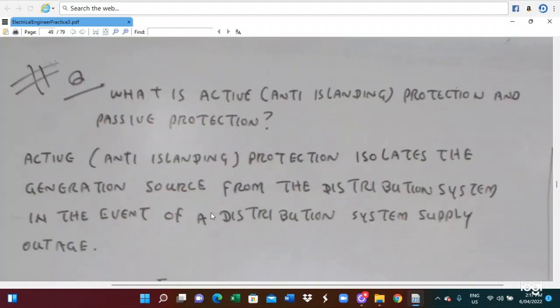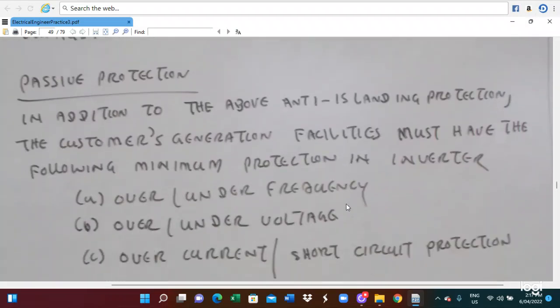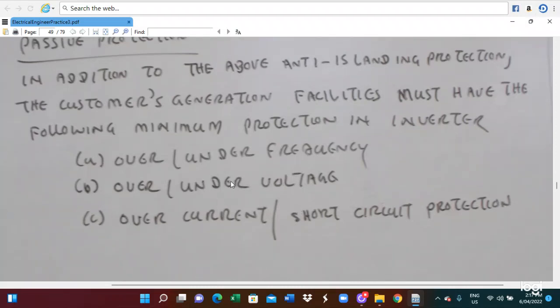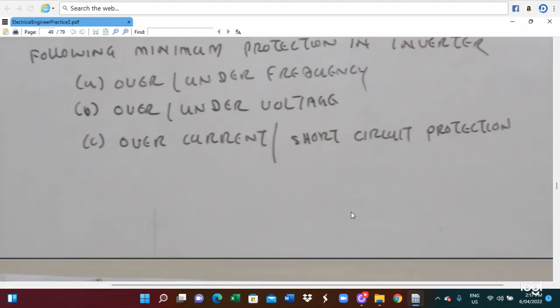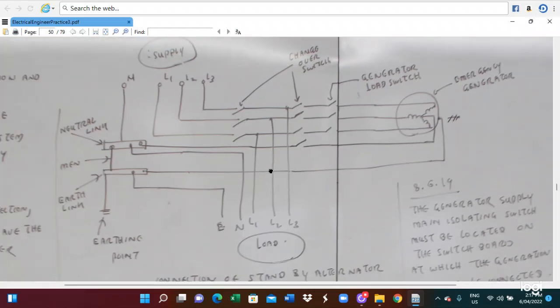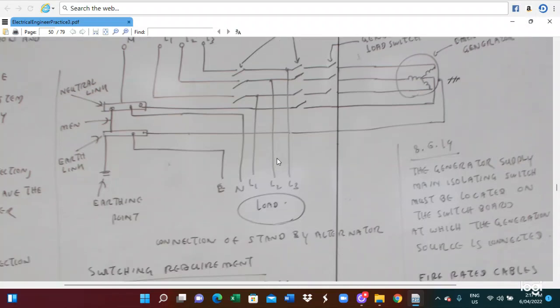What is the difference between active anti-islanding protection and passive protection? Active island protection isolates the generation source from the distribution system in the event of distribution system supply failure. Passive protection, in addition to the above anti-islanding protection: the customer generation facilities must have the following minimum protection in the inverter. They must have over and under voltage and frequency protection, over and under voltage sensors, and overcurrent and short circuit protection. Those are the requirements. So this is the diagram of the three-phase generator, load, and changeover switch, and the supply connection. This is the main neutral link, the earth link, the load, the generator, and the supply changeover. Emergency system and normal system connection diagram.